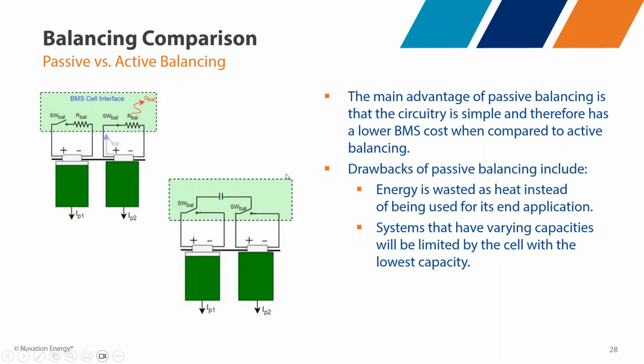In a passive balancing application, the system is limited by the state of health of the lowest cell in a stack, whereas in an active balancing system, you're limited more by the average of cells within a stack. That's one of the key advantages of active balancing.